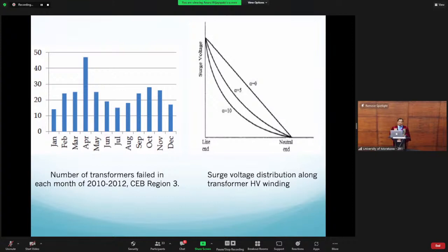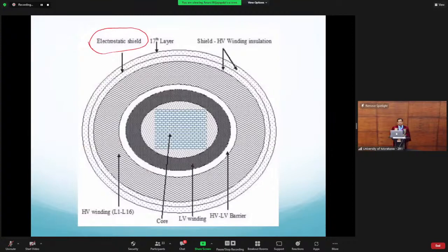Then we looked at the right-hand side graph, which is very famous in our electricity theories. Professor Lucas used to teach us, Professor Sam Karunanandan used to teach us, and you can see that there are 3 curves showing how the surge voltage will spread across the transformer winding from the line end to neutral end. And you can see when this parameter called alpha is 10, on a few number of turns, a large voltage quantity appears. Large voltage drop is there. But as alpha is 0, you can see the voltage is more uniformly distributed. Therefore, the chance of initial turns getting insulation failed is less. So we looked at how to apply this. We proposed an electrostatic shield between the last layer and the next layer. That is simply an aluminium foil to be connected to ground.